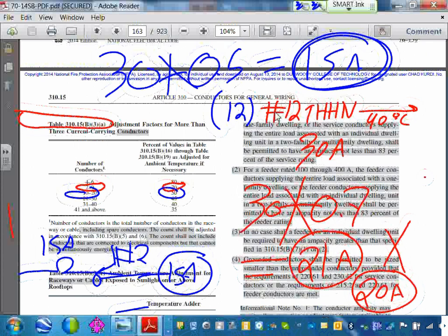But anyway, remember, you only need six circuits in a pipe. You put more than six circuits in a pipe, 20 amp circuits, what do you need to do? Drop the load. Not a good idea. Any comments, any questions about this?